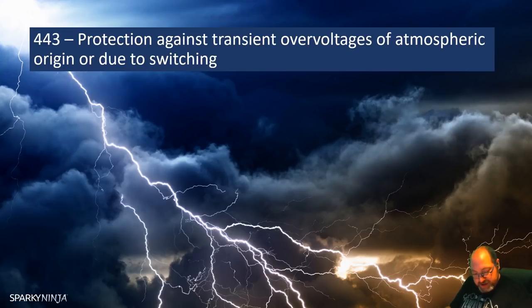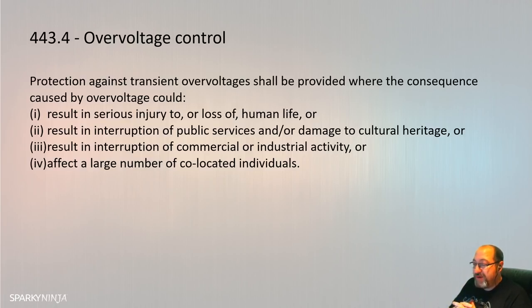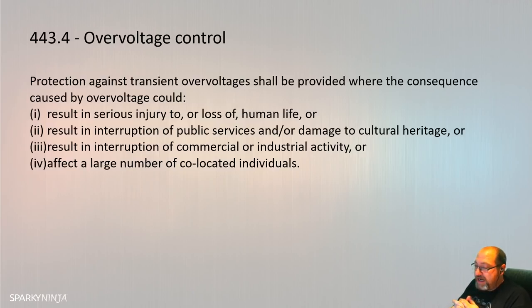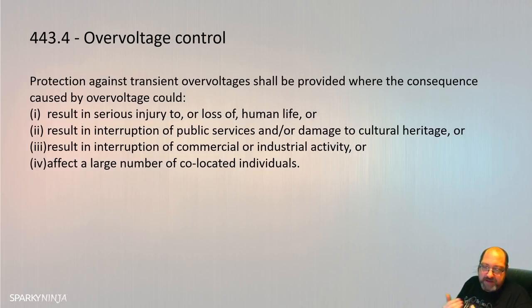Section 443.4 — overvoltage control. Protection against transient overvoltages shall be provided where the consequences could result in serious injury or loss of human life, interruption of public services or damage to cultural heritage, interruption of commercial or industrial activity, or affect a large number of co-located individuals. With regards to this consideration, you have to ask what the consequence is — if it's a risk to human life or a risk of disruption to business, then there is a need to consider it.